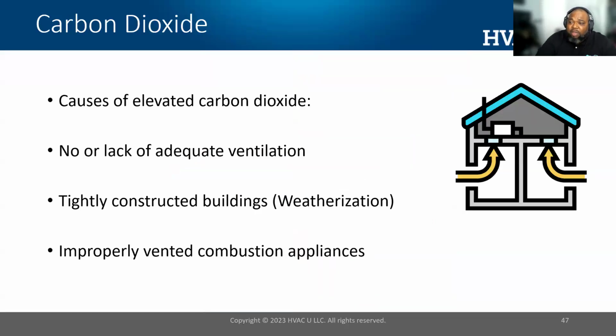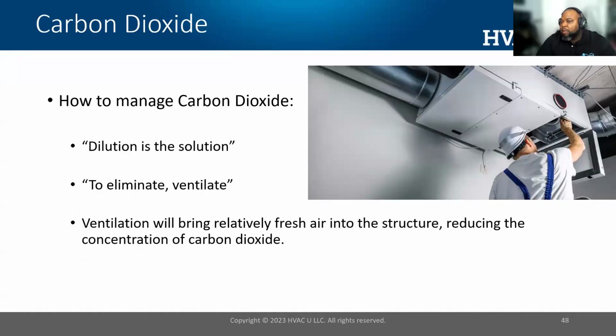All right. Causes of elevated carbon dioxide. Buildings where there's a lack of adequate ventilation, where the building maybe was weatherized and there wasn't a strategic ventilation plan. Carbon dioxide can also come from improperly utilized or unvented combustion appliances. How to manage carbon dioxide? Like we said, we want to dilute it. Dilution is the solution, and to eliminate, ventilate. Using some type of ventilation device, a strategy that's appropriately sized and installed and commissioned will help to reduce those carbon dioxide levels. Ventilation is bringing fresh air in, relatively fresh compared to inside, which will help to reduce that concentration of carbon dioxide.